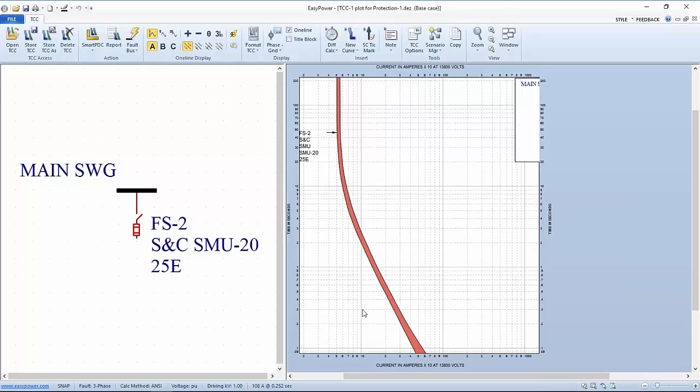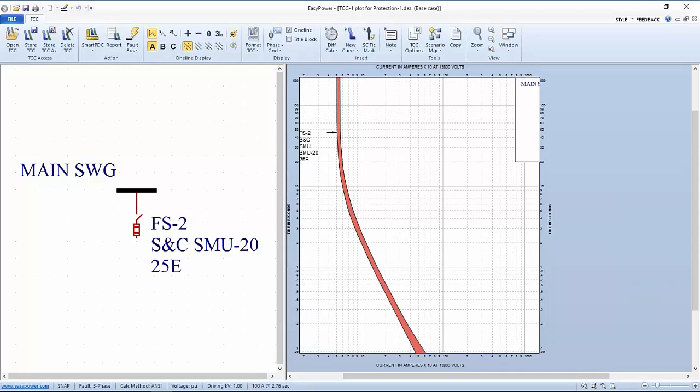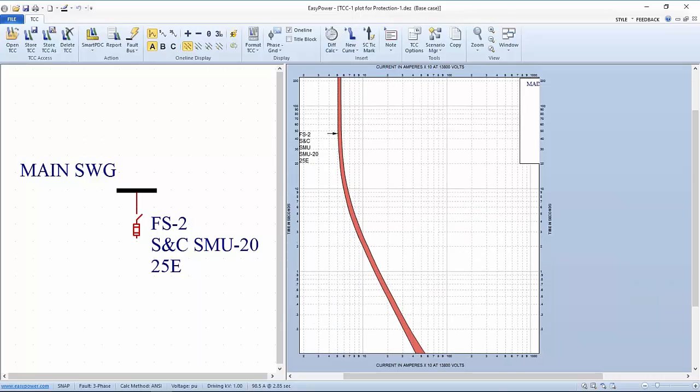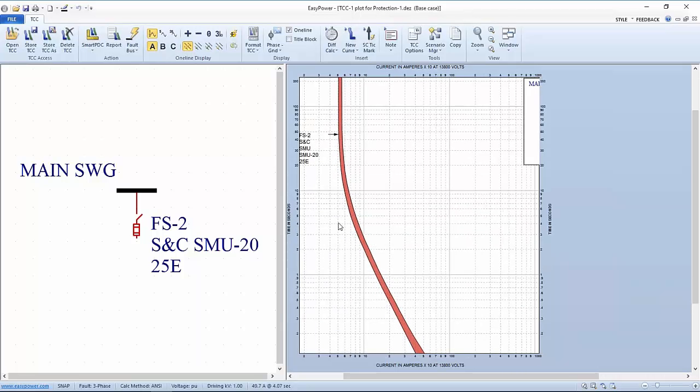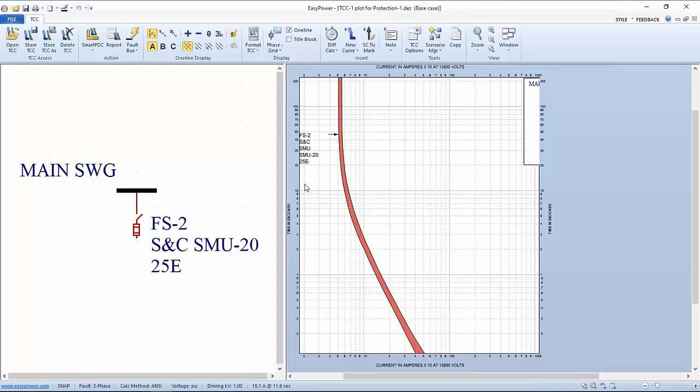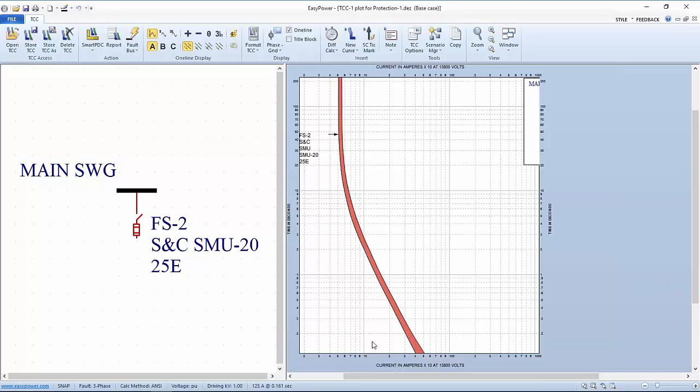The tool shows me, if I look down here at the bottom of the screen, shows me the coordinates of wherever I have the mouse cursor. If I come up to the performance curve on this fuse and I put the cursor there, I can see that I'm displaying a point that represents 53.1 amps and 44.2 seconds, which means if I have a current at this point for that long, there's a potential that the fuse will engage and clear. As I look at the thickness of this fuse curve, it represents the uncertainty factor or the range of values that could occur within any particular fuse.